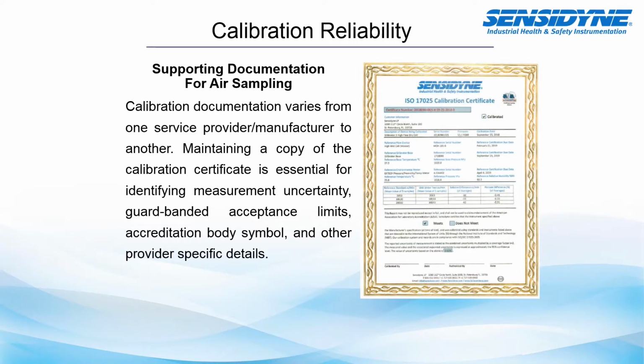Some additional supporting documentation that you want to hold on to is your calibration document for your calibrator itself. Now, this is a certificate that your service provider or manufacturer provides. Maintaining a copy of the calibration certificate is essential for identifying measurement uncertainty, guard-banded and acceptance limits by the accreditation body, as well as other provided specific details associated with your calibration device.